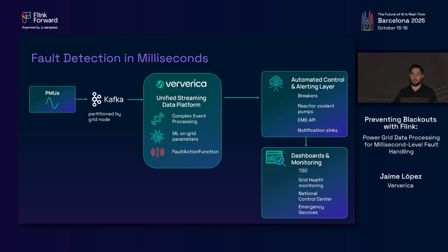Okay, we've done everything we could to prevent trouble and to predict trouble, but at some point we have to take action. So you also can have within our unified streaming data platform a simple job, a fault action function, a job that's going to tell the system what needs to happen now that a fault has been detected. And within this very small latency of 100 to 200 milliseconds, you can action this and send it to the automated control and alerting layer, which are physical devices that already exist in the grid.